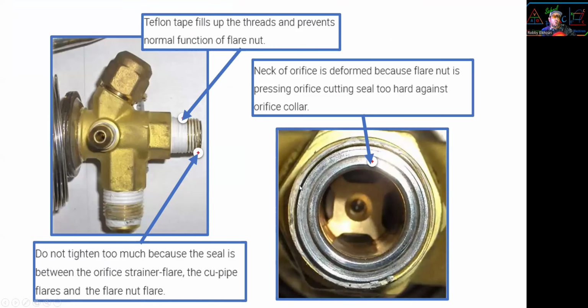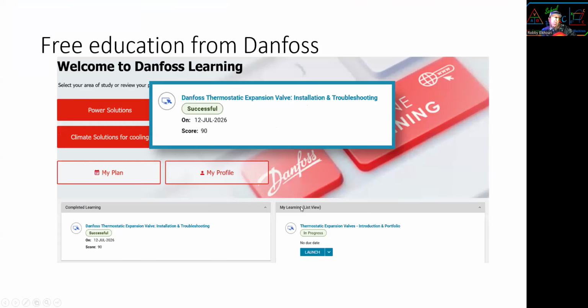Now, do not use Teflon tape. This is from Danfoss Learning. Teflon tape will fill up the thread, preventing normal friction of the flare nut. Do not over tighten, because if you over tighten, you could damage it. And you can see here, the Teflon tape could go inside and cause damage. No need for Teflon tape on a compression fitting. All right, now, a free education from Danfoss.